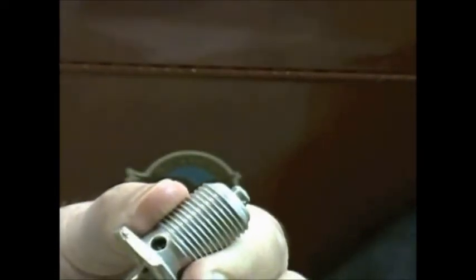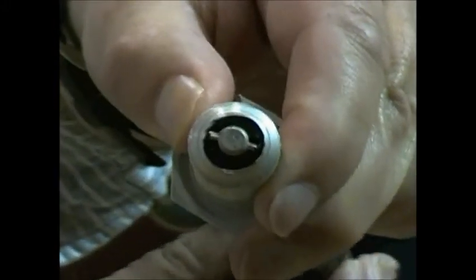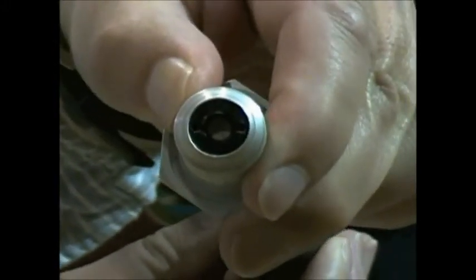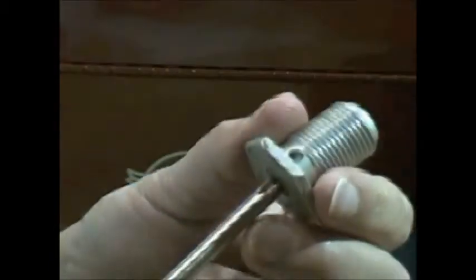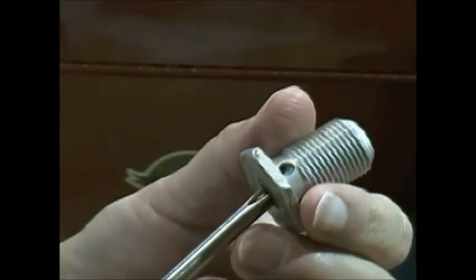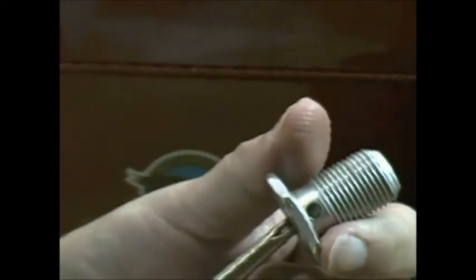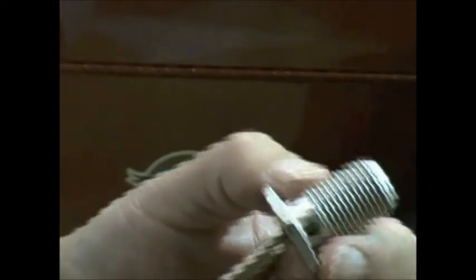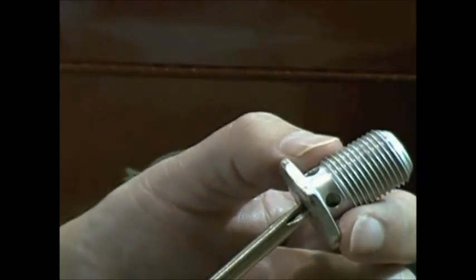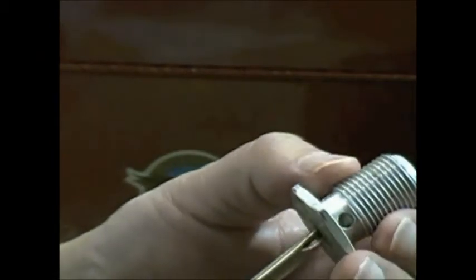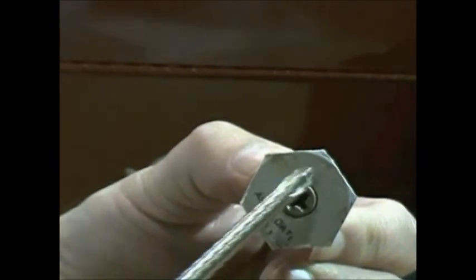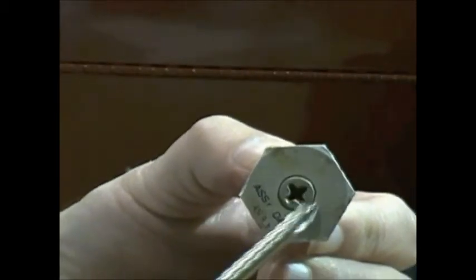And you're going to have to wiggle it around and hope that this plunger, as you rotate it, snaps back into the closed position. Now that's one of the many maintenance advantages to having this kind of a sump drain. Sometimes the drain will leak, the fuel will leak around the O-ring of this plunger.